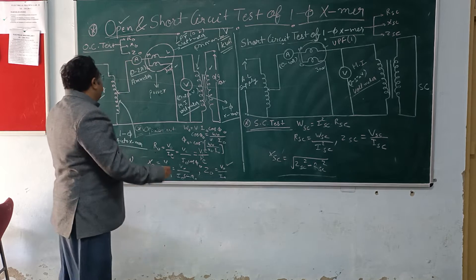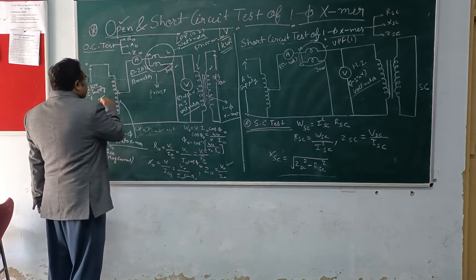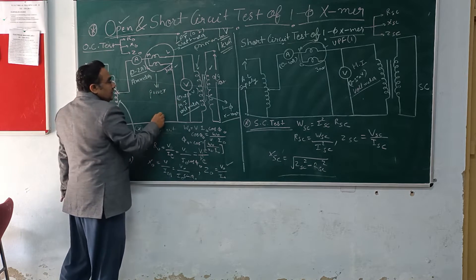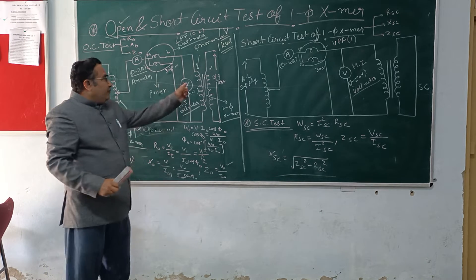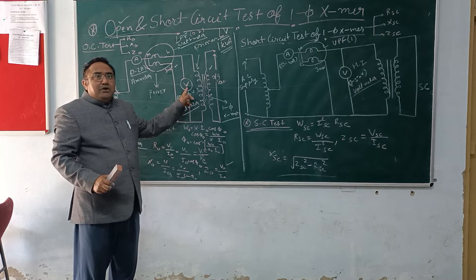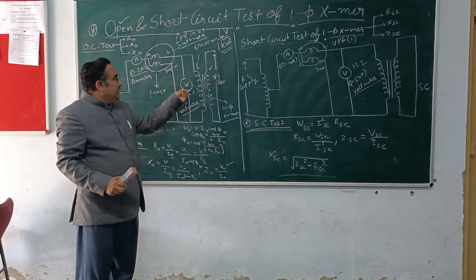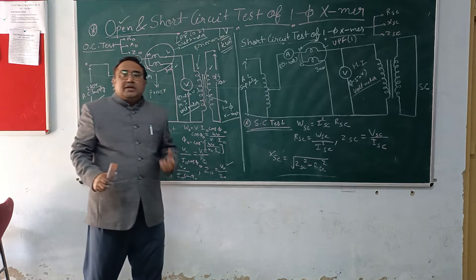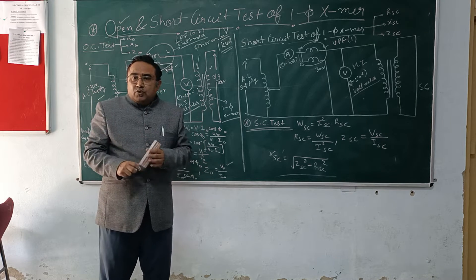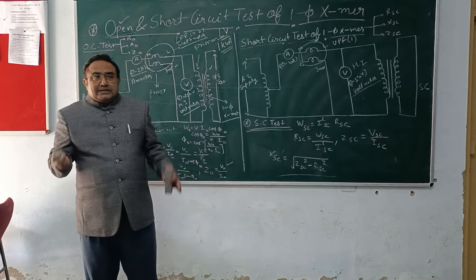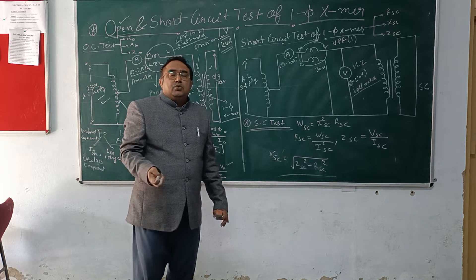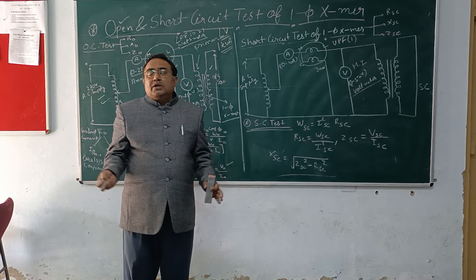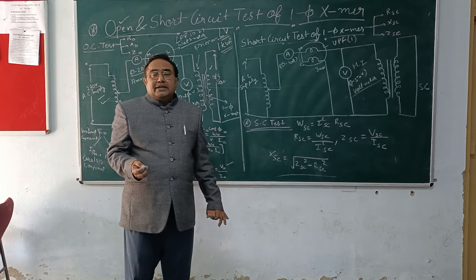Why? Performing on the low voltage side means the AC supply source is always connected on the low voltage winding side, because if we perform on the low voltage side, we will have easy availability of voltmeters of laboratory range - that is 0 to 300 volt or 0 to 500 volt. But if we perform on the high voltage side, such type of bigger instruments to measure quantities like 11 kV or 33 kV are not available in our laboratories.